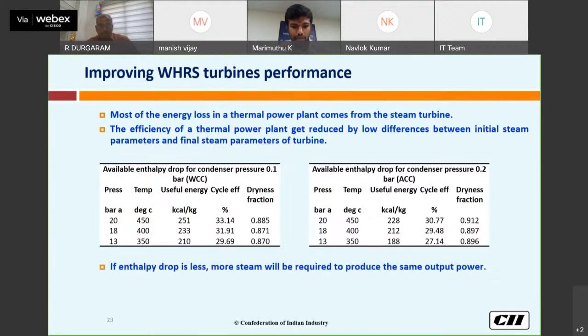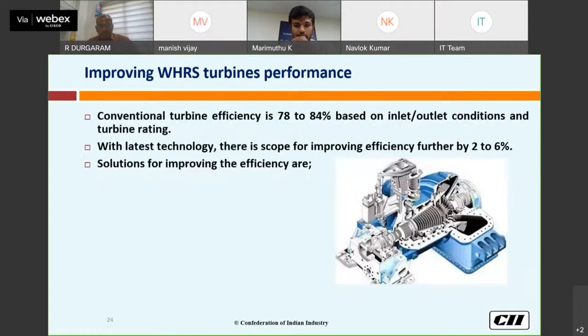Now you can see in the table on the left side. If the main steam temperature is high, my cycle efficiency will be 33. If it is less, for example 13 bar and 350 degrees, the efficiency goes down. So if the enthalpy drop is less, more steam will be required to produce the same power. So that's why we are getting low efficiency in the WHRS turbine.